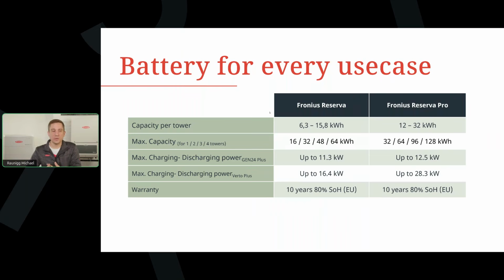With that, we have a maximum charging and discharging power with the Gen 24 Plus with the Reserva Pro of up to 12.5 kilowatts, so nearly the maximum of the Gen 24. And especially with the Verto Plus, this is a very nice feature, we have up to 28.3 kilowatts of charging and discharging power. For farming applications, multifamily houses, everywhere where you need a high peak load, you can now cover this combination of Reserva Pro together with the Verto Plus, and you will get a very nice charging and discharging rate of nearly 30 kilowatts of power.